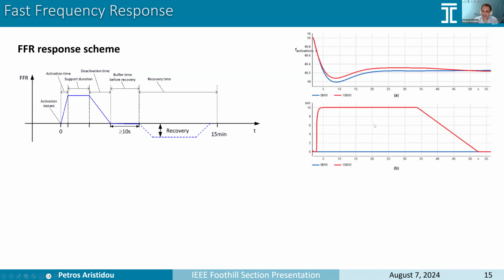If we see here the simulation, again, the blue line is without fast frequency response schemes. So we see that we have a lower nadir, and if we add here 10 megawatt of fast frequency response, then this nadir is pushed upwards. We don't see any difference in the rate of change of frequency because the activation time is not fast enough. These are not grid-forming units, so they have a slower activation time. So the rate of change of frequency does not change. The post-fault steady state does not change. The required inertia and the required FCR do not change. The only thing that we impact is this nadir here.